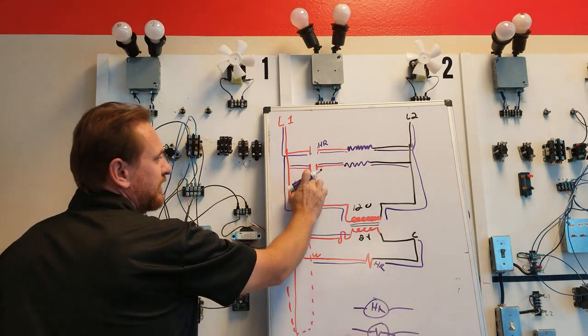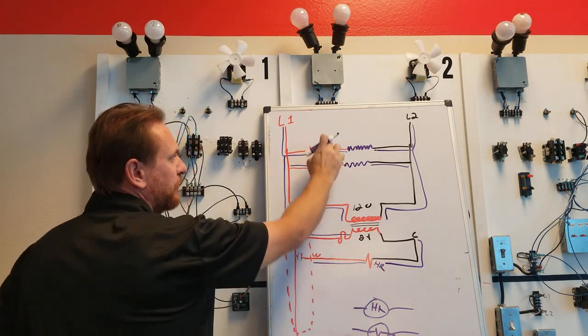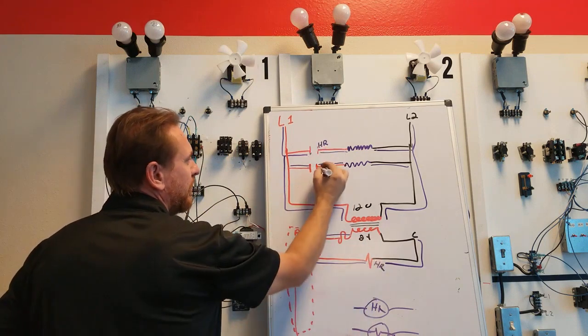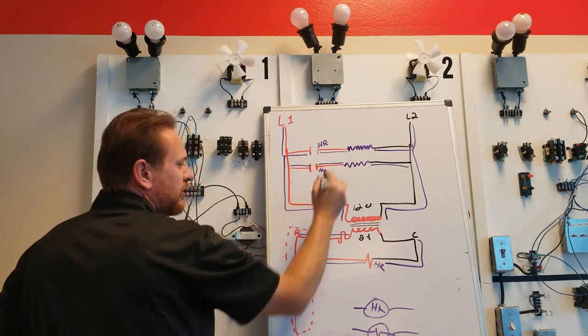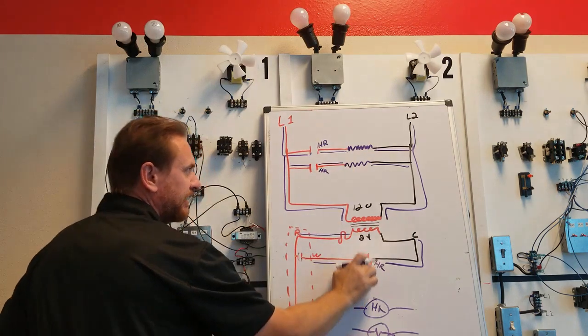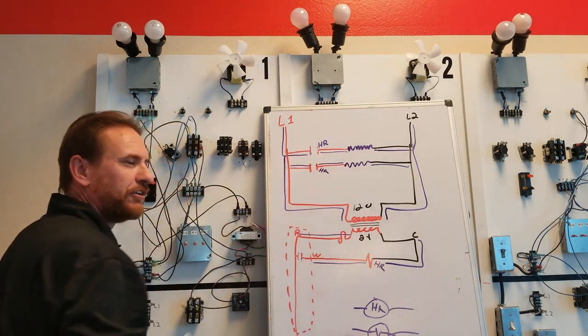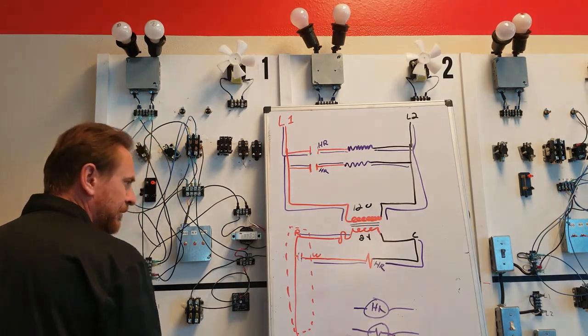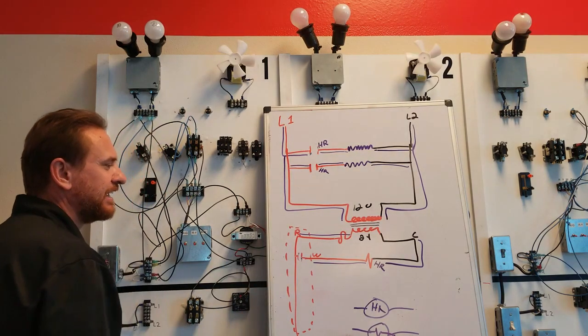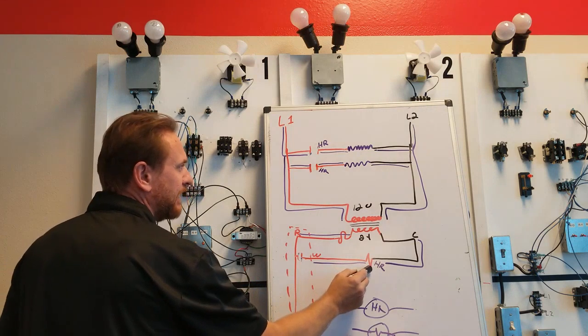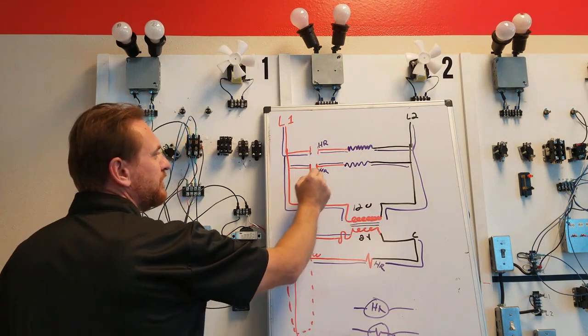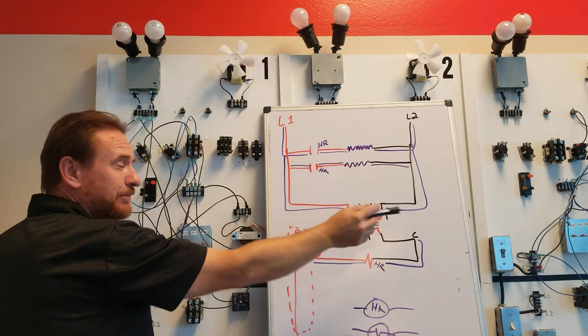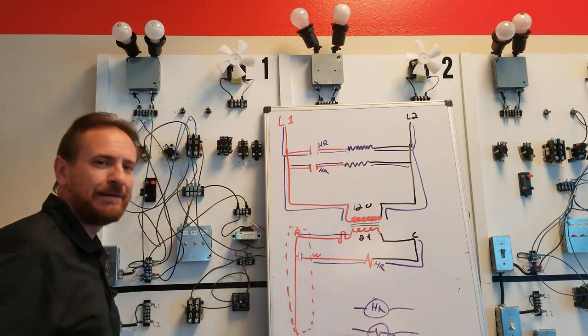But I have this switch that's unlabeled. This HR controls this switch, and this HR is also going to control this switch. So I know if I put 24 volts here, this will close and this will also close. Sequence of operation: thermostat calls for heating, connects R and W, energizes my electromagnet, which closes this switch, sending power to this light bulb or heat element, and closes this switch, sending power to that light bulb or heat element.